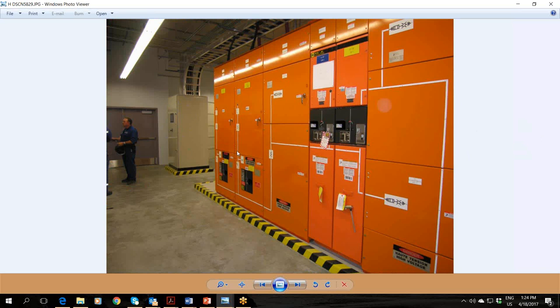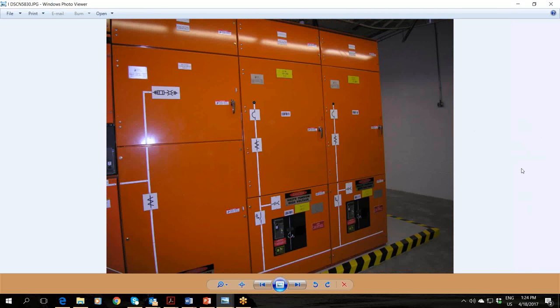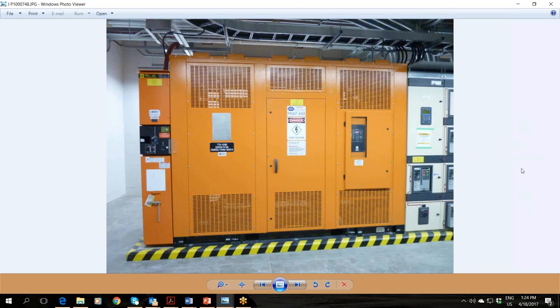Something just to point out, this is a protection and control cabinet, so the protective relays associated with these breakers are inside of this cabinet here. And it's got a little touchscreen HMI as well for electrical control of these breakers from here. You don't have to operate them from the front.